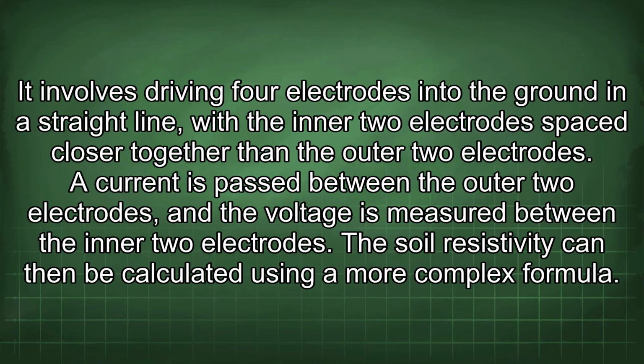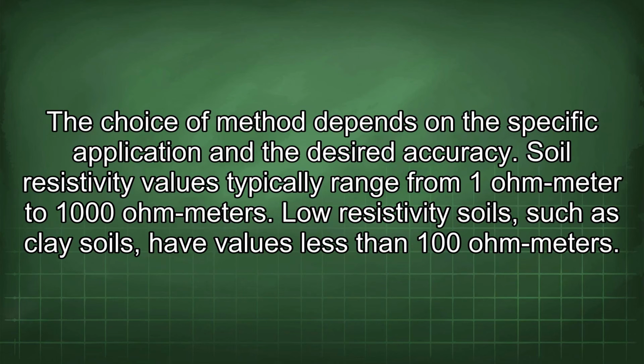The Schlumberger array method is another method for measuring soil resistivity. It involves driving 4 electrodes into the ground in a straight line, with the inner 2 electrodes spaced closer together than the outer 2 electrodes. A current is passed between the outer 2 electrodes, and the voltage is measured between the inner 2 electrodes. The soil resistivity can then be calculated using a more complex formula. The choice of method depends on the specific application and the desired accuracy.